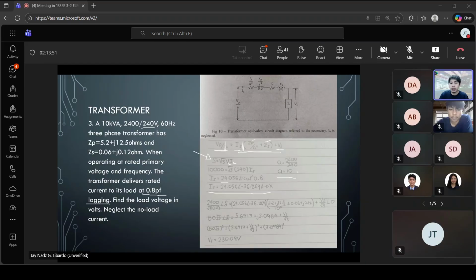Now we need to get the values for VS, so we need to identify VP. Since the problem doesn't state a specific input voltage, we will use 2,400 as the default. Remember, if the problem doesn't state the input voltage for the transformer, we use the rated voltage of the primary as default, which is why we use 2,400 here.